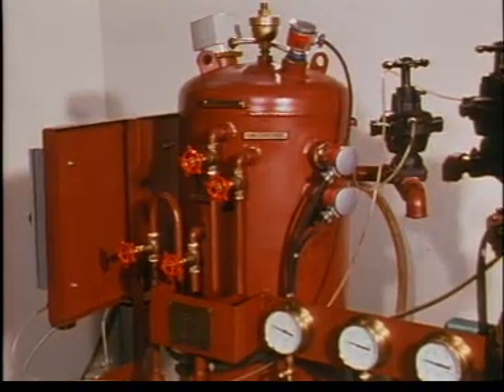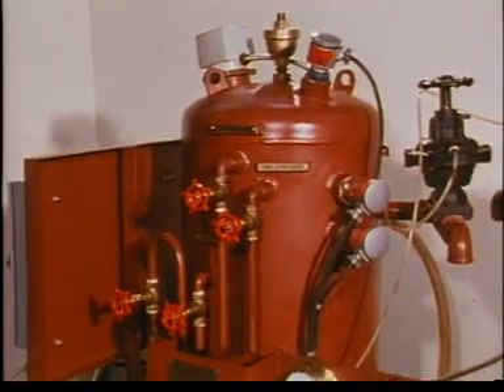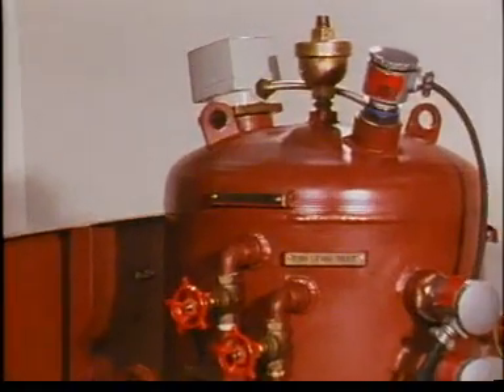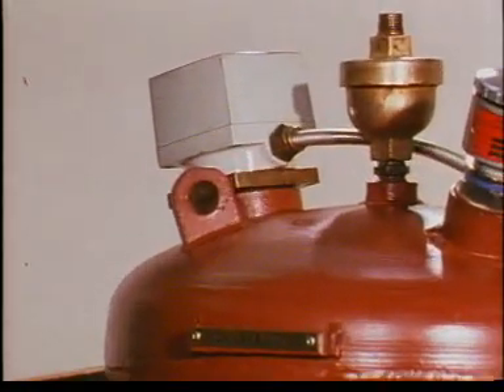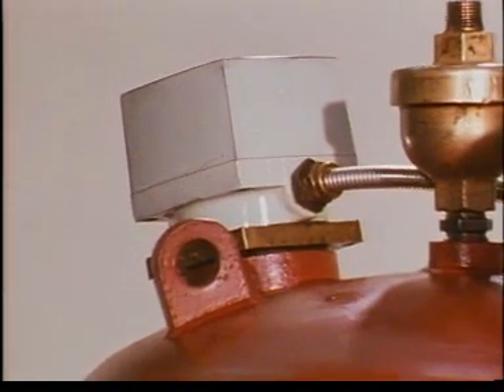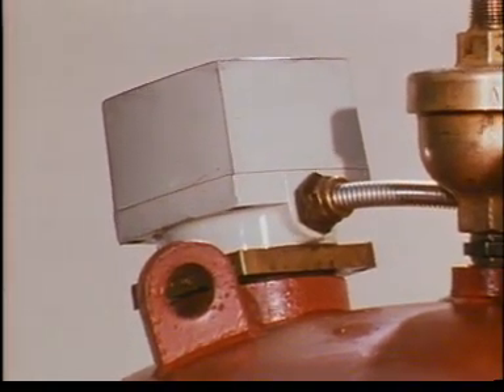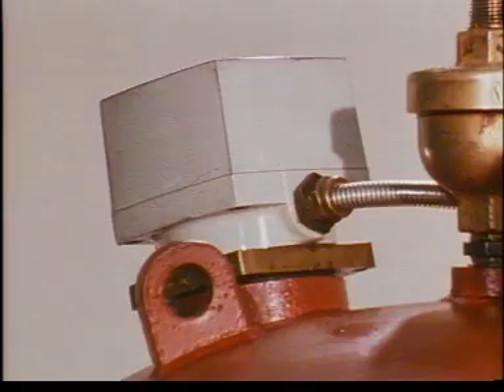In very cold conditions, or when the oily water contains heavy fuel oil, both slowing operation time, it is sometimes desirable to heat the upper part of the separator to facilitate separation. An electric immersion heater is therefore fitted.